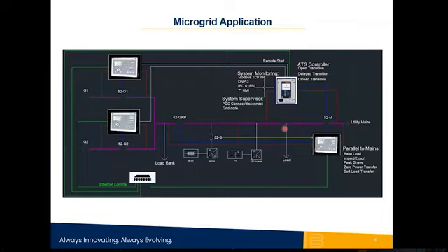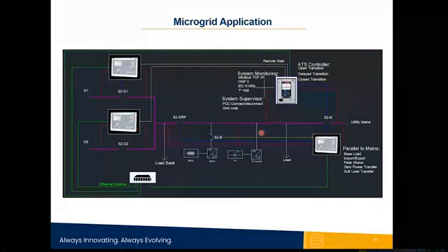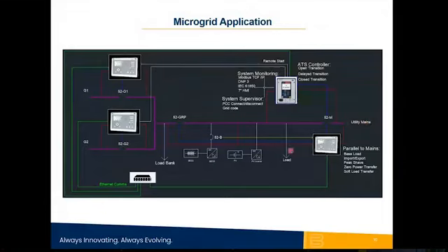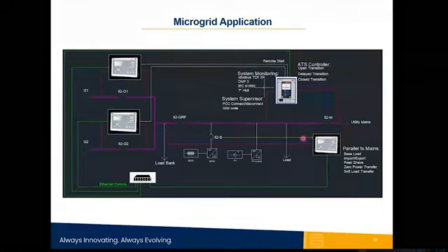We have some loads here. The loads can be supplied either by the generators, the BESS system, the PV system, or all of the above when the system is disconnected from the grid. And then we have the grid on this side. We may have the normal source of power as the utility supplying the loads this way. Then we can reconfigure the system in several different ways. We can connect to the grid and export power. If the grid is not available, then the local resources here can supply power to the loads. And there are many, many things we can do.